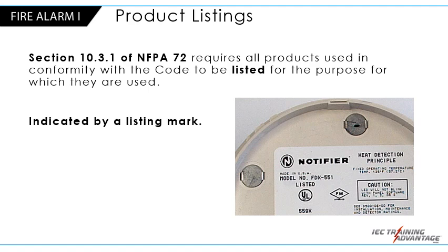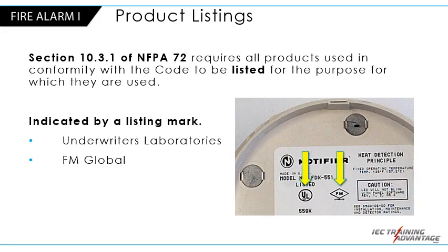As was stated, NFPA 72 requires that all of its products be listed. Product listings are found in section 10.3.1 of NFPA 72, and this requires all products used in conformity with the code to be listed for the purpose for which they are used. This listing is indicated by a listing mark on appliances by Underwriters Laboratories, FM Global, and those symbols can be located here on the smoke detector or initiating device appliance. UL lists products, whereas FM approves products. These two terms essentially mean the same thing.